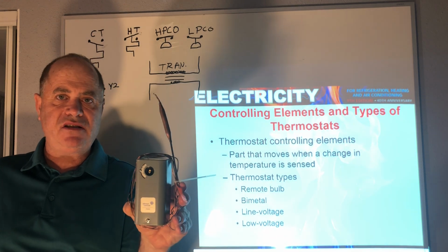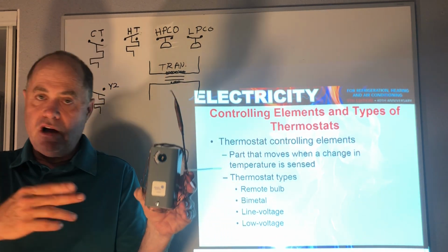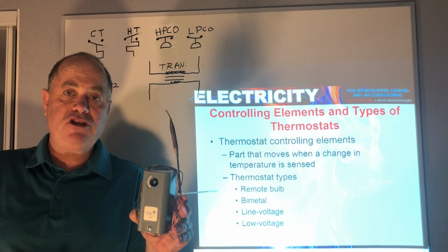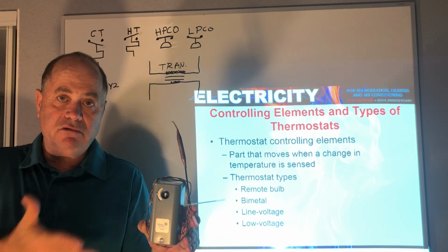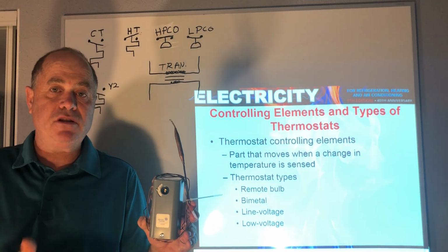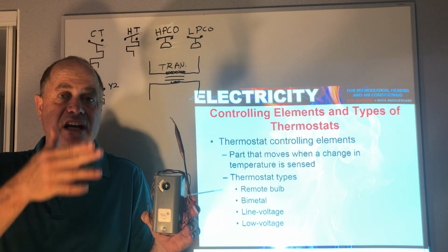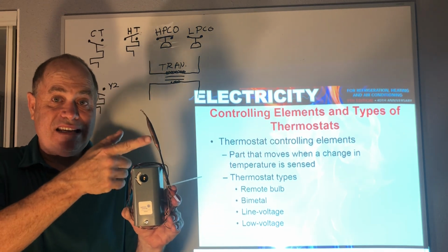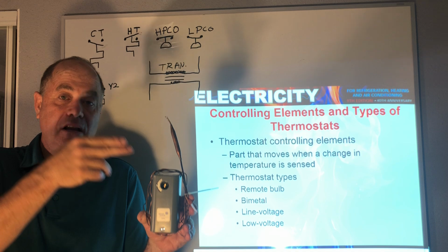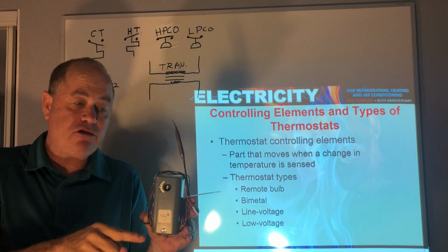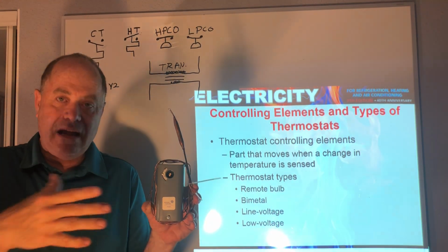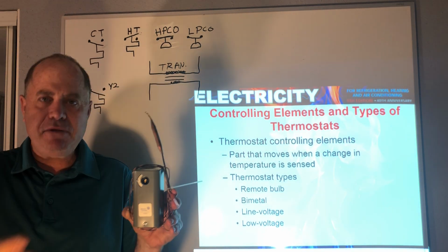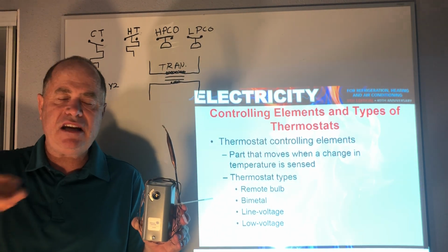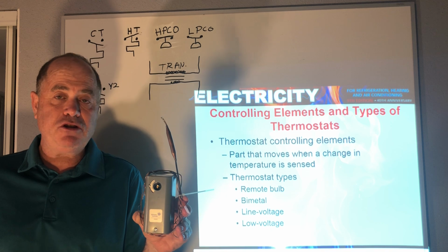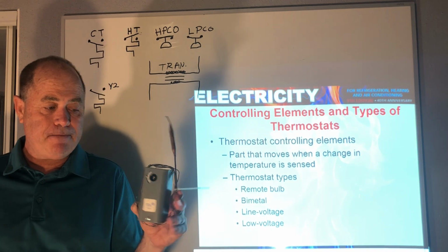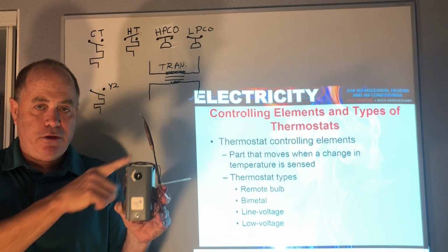Let's say the box gets to 41 degrees, the contact closes, the refrigeration compressor comes on, it runs and runs and runs, and the temperature in the box drops to 35 degrees, we'll say. The thermostat says, hey, I sense that it's cold enough. Let's open our contacts, and then no electricity flows through the thermostat, and we shut the cooling off. And this happens over and over again so that we maintain a constant temperature in our refrigerated box. Okay, so this is a remote bulb thermostat.